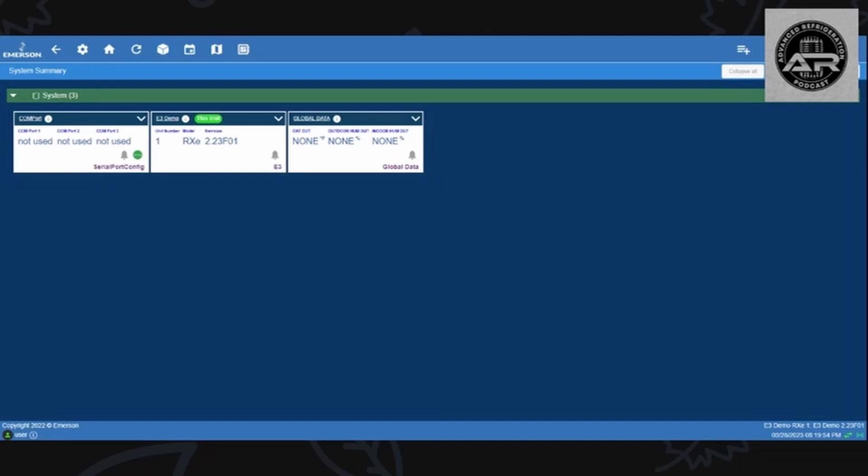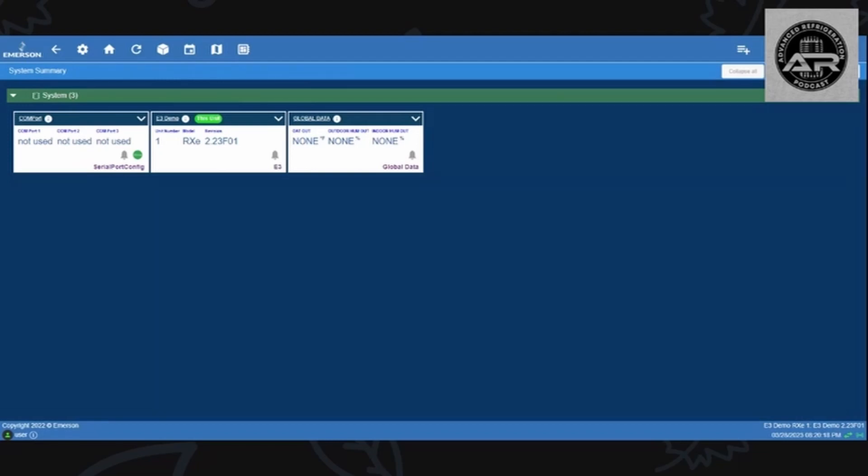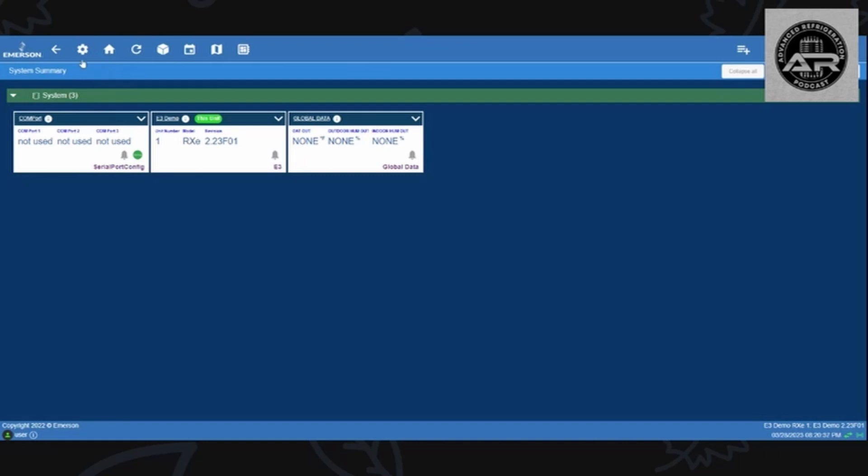If you have any of the E models or the old 400 models, you have the ability to add more applications if need be. The applications come as a license based, so you have to reach out to whoever your Emerson account manager is and get a quote to add additional licenses. To do that you need the MAC address. Is there still a license matrix like the E2 had that shows what they all have? Yeah exactly, there's the matrix. The current matrix shows site supervisor as well as the E3 and it shows the CX, BX, RX, X amount of suction groups, condenser applications, it shows all that stuff.